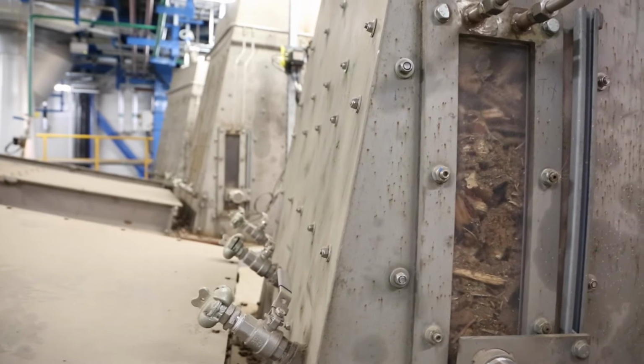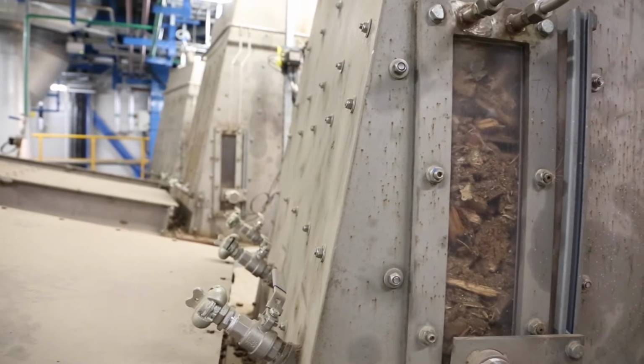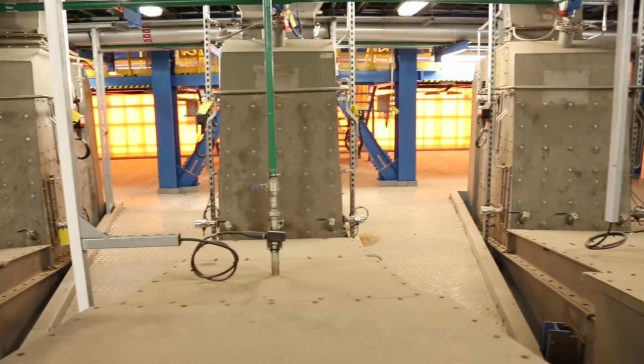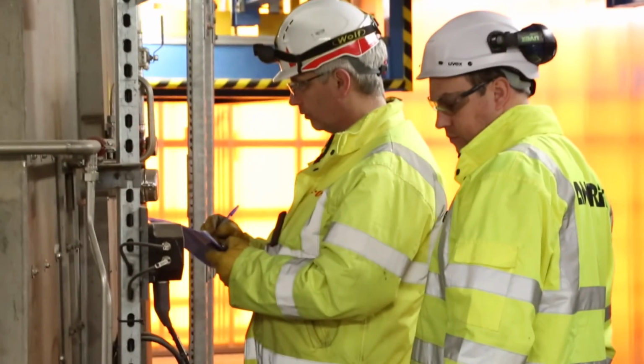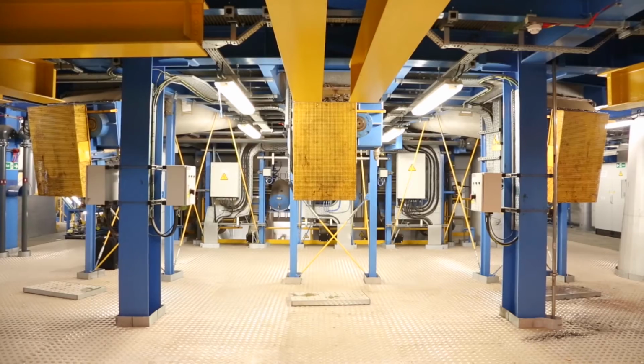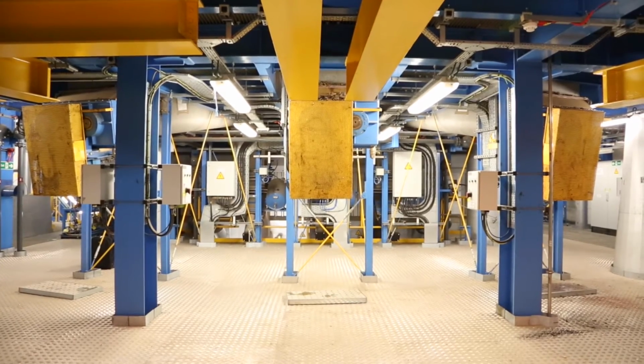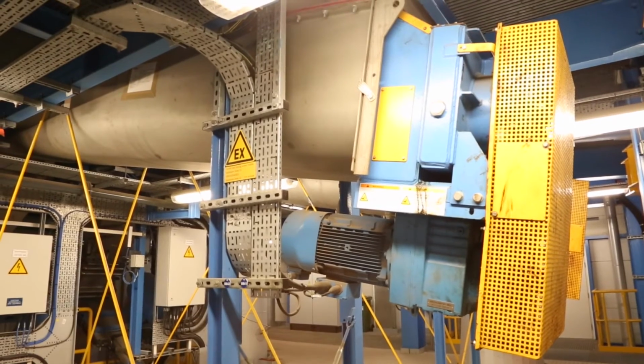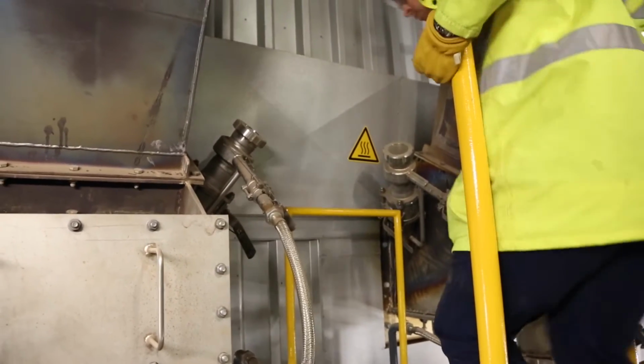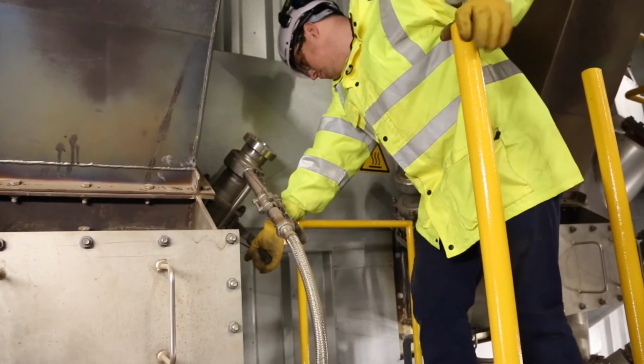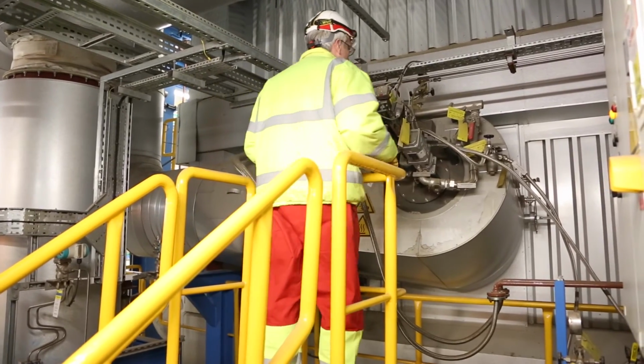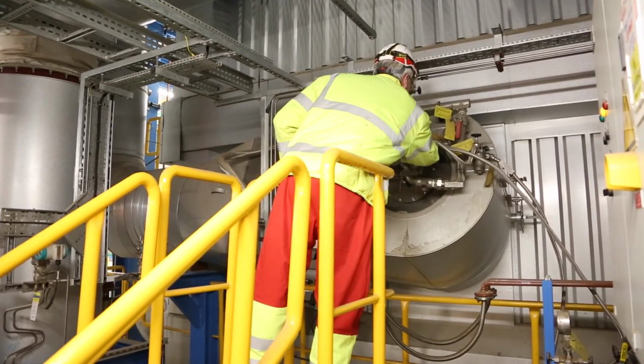The recycled wood stored in the day silo is loosened by a rotor and subsequently falls into the troughs of the discharge screws, which discharge the fuel into one of 3 dosing bins. These dosing bins, together with the dosing screws, serve as an airtight seal to the boiler. Double screw conveyors extract the fuel out of the dosing bin. The DCS controls the speed of these double screw conveyors as a function of the boiler load. Finally, the fuel is injected via air-supported injection ports onto the fluidized bed. For the startup of the fluidized bed boiler, 4 burners are installed.